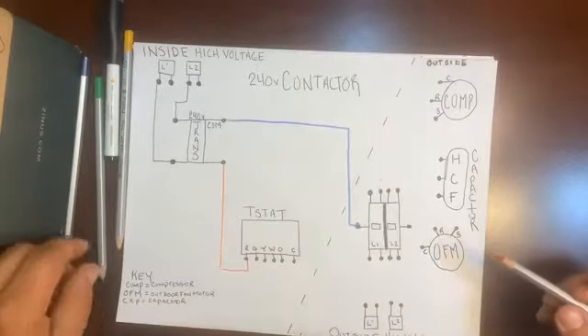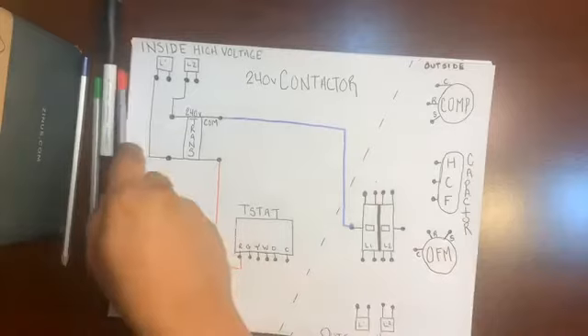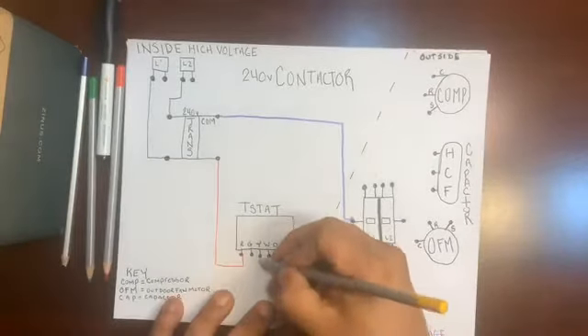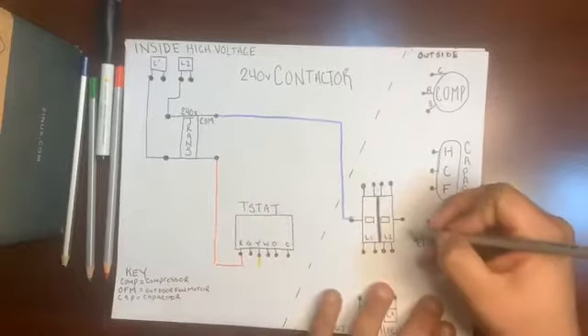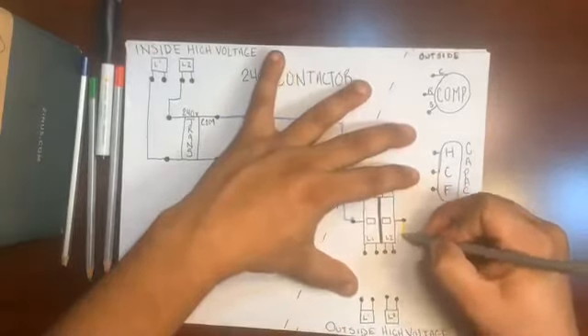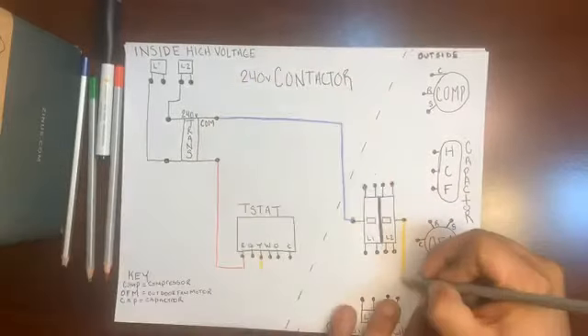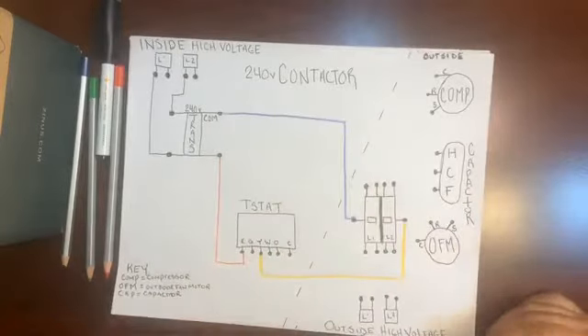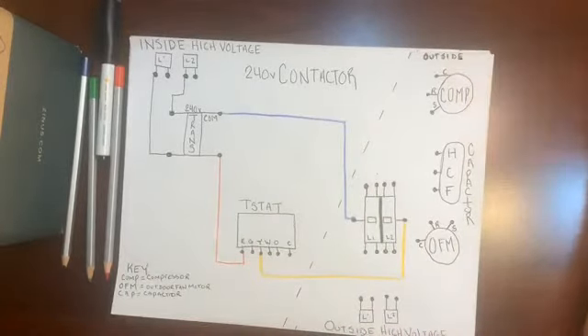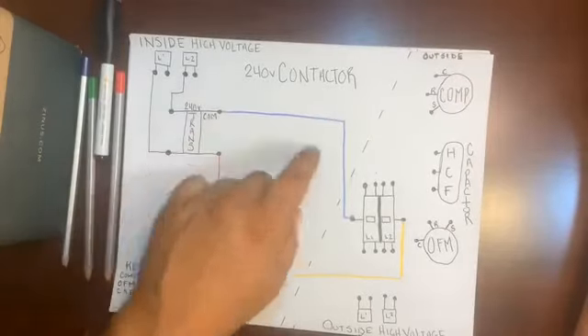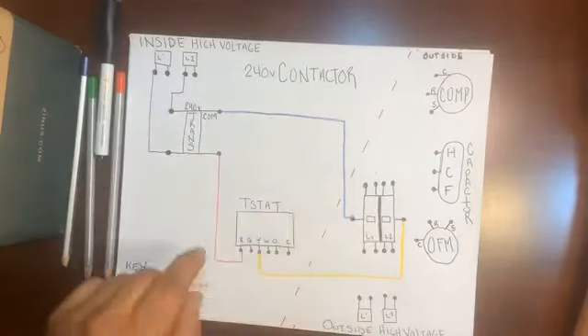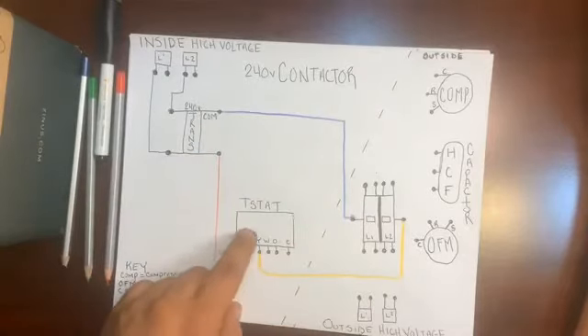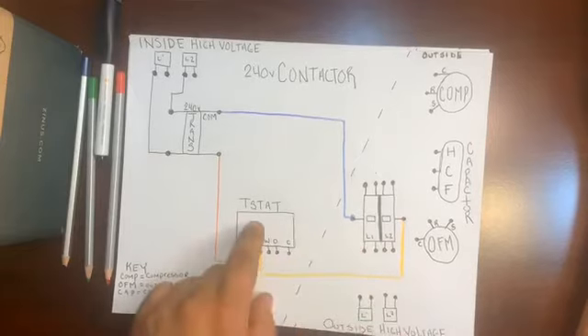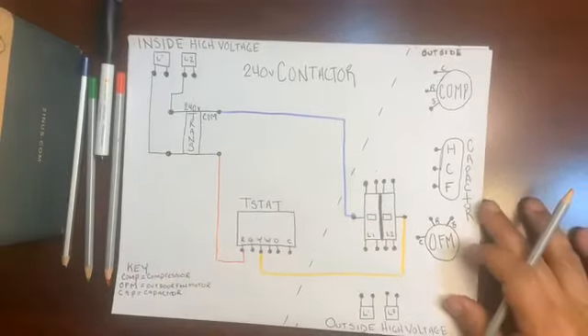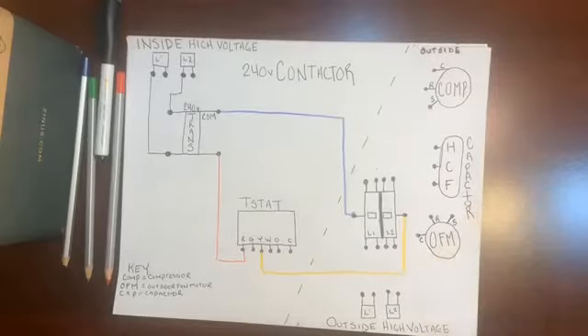So let's go ahead and let's run our yellow. We're gonna run our yellow, our control. We're leaving the yellow on the thermostat. Let's bring this down pretty tight here. And then we'll bring it over. All right, before we even get into the high voltage connections outside, we'll go over our transformer, our 24 volts, common coming to every leg of the relay, put it in the hand, and then control coming down into the thermostat, and then the thermostat sending the voltage over when the thermostat says, engage Mr. Contactor. So now let's go ahead and get some high voltage knocked out here.